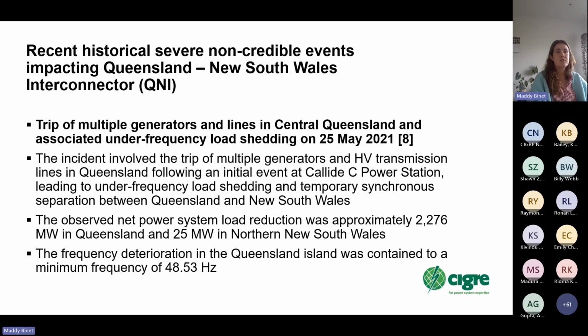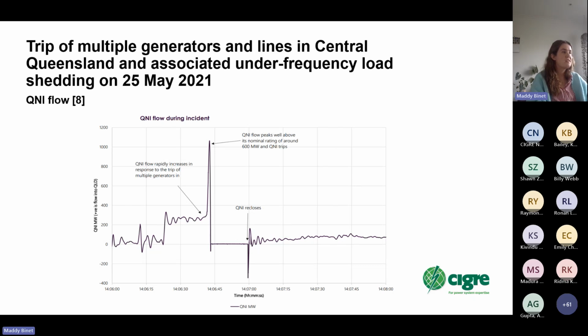This ultimately led to the tripping of multiple generators and transmission elements in Queensland following the initial Callide C event, which then led to under-frequency load shedding and the QNI AC interconnector between Queensland and New South Wales tripping, causing synchronous separation of Queensland. The minimum frequency in Queensland dropped to 48.53 hertz, below the UFLS threshold of 49 hertz. This figure shows the QNI flow during the incident.